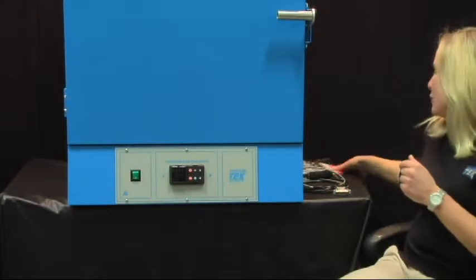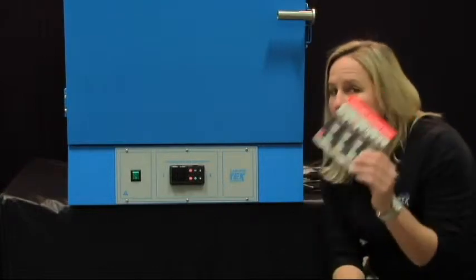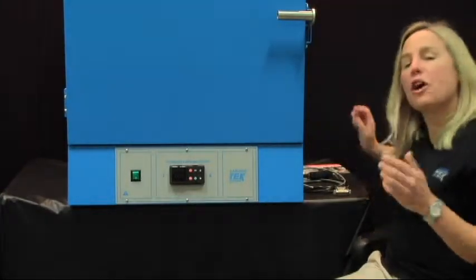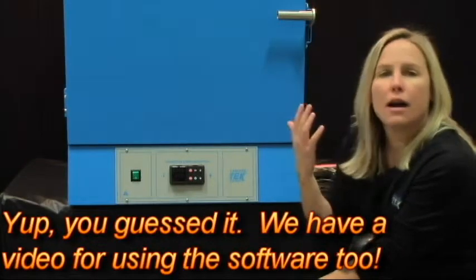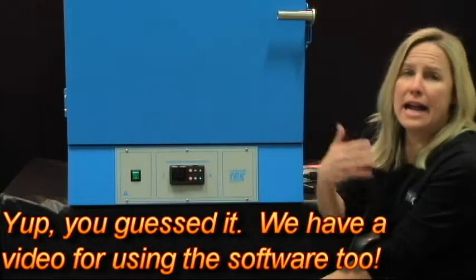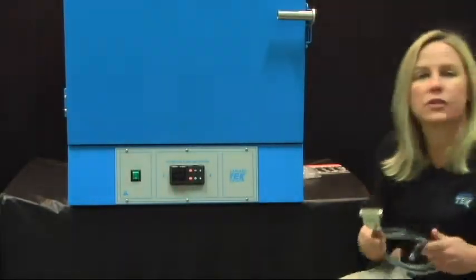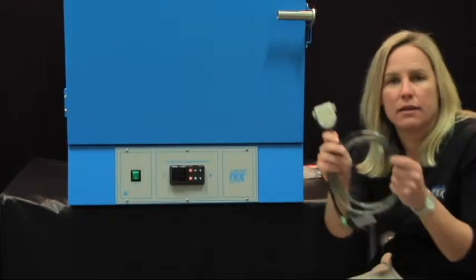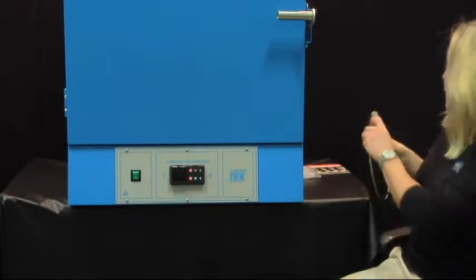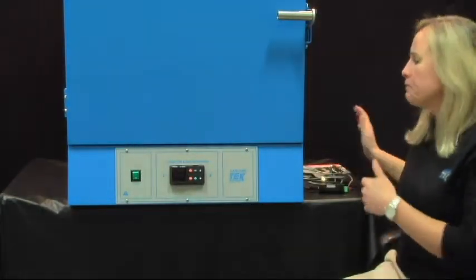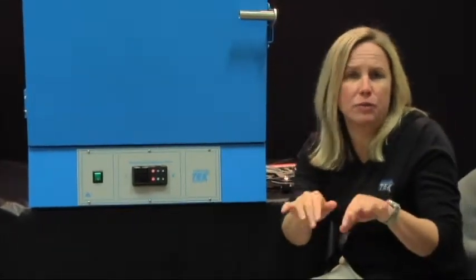What's great about this controller is that it comes with a free piece of software called the configurator software. This will be with your manual. Installing that on your computer will allow you to program your Watlow controller, save the settings, and watch the controller in action if it is, in fact, plugged in. So, Cascade Tech can provide you with the RS-485 D-pin connection cable to USB connection to your computer. That will allow you to actually program and interface with this controller via your Windows-based computer environment.